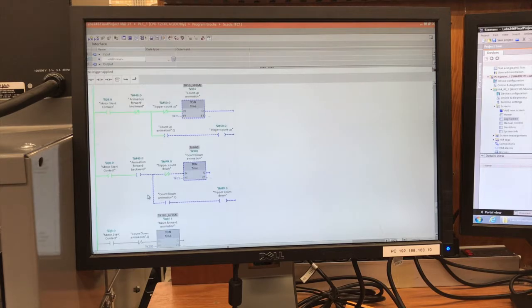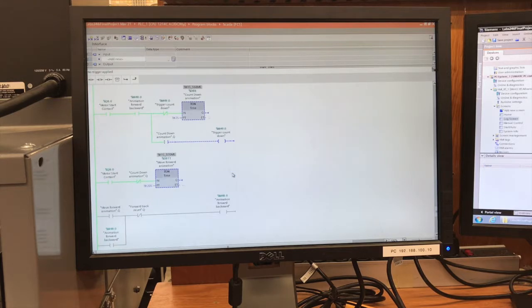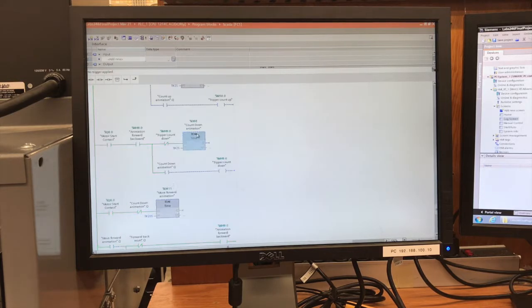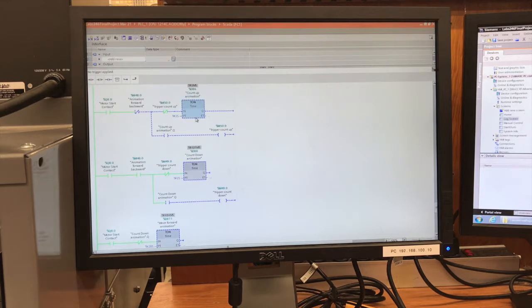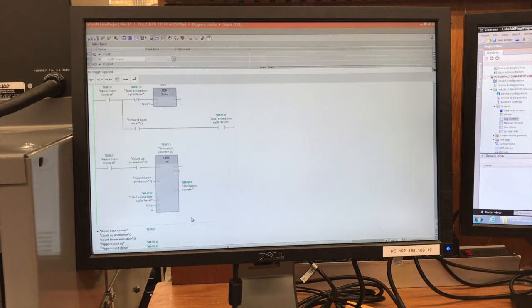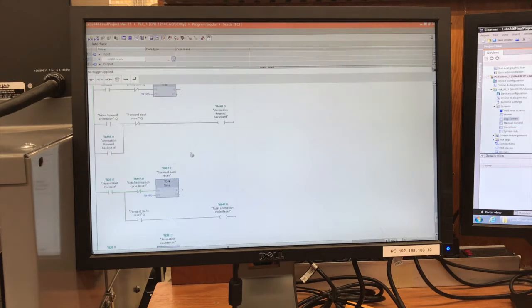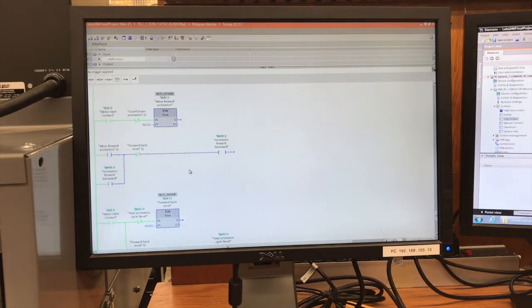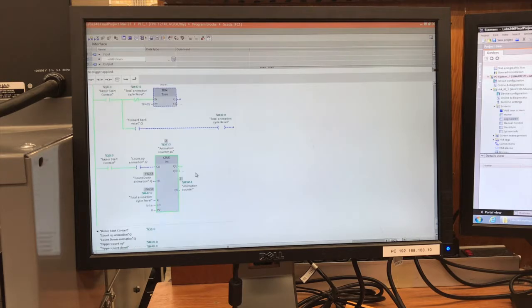Now this one shows the animation counter that we created. This one actually moves our turner back and forth in the PC system. Again, it's a count up, count down timer. It uses two different TONs to control its up and down movement, and then also has a reset. So after our period of 40 seconds, it will reset the entire system. And after 20 seconds, it'll latch it in its one condition, so that it can go forwards or backwards. And that's how we get our turner to move back and forth.